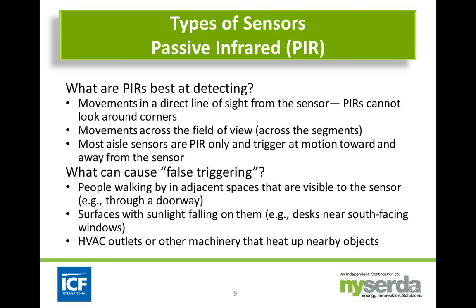There are things that could potentially cause false triggering, such as people walking by an adjacent space that might be visible to the sensor. And we'll talk about under the commissioning section how you can avoid some of those problems. If a surface has significant sunlight, or an HVAC outlet that's in a particular space can actually create some heat motion that might falsely trigger the sensor and leave the lights on.